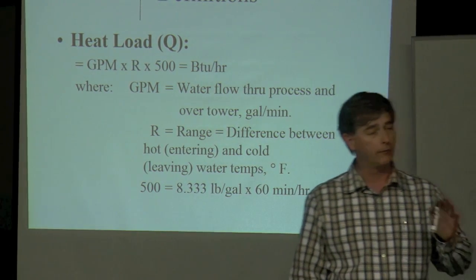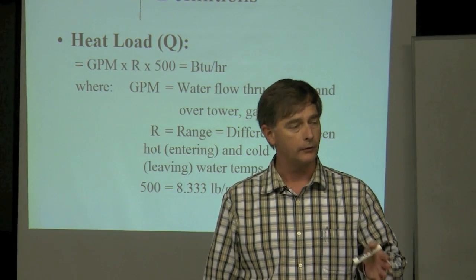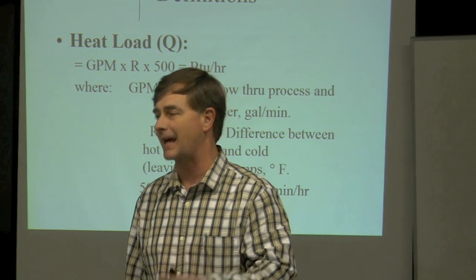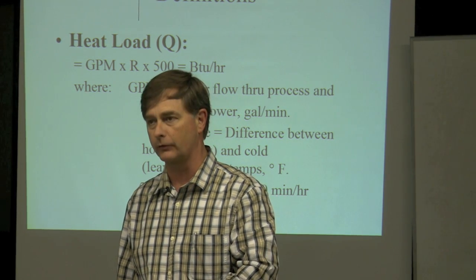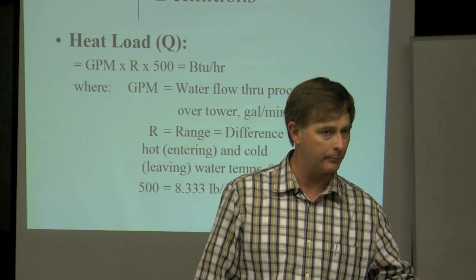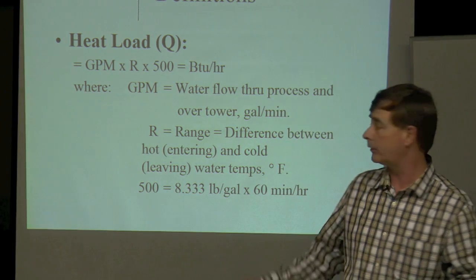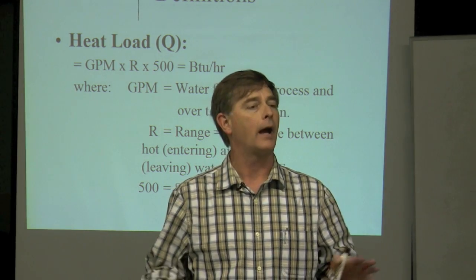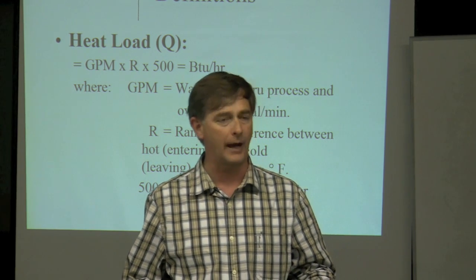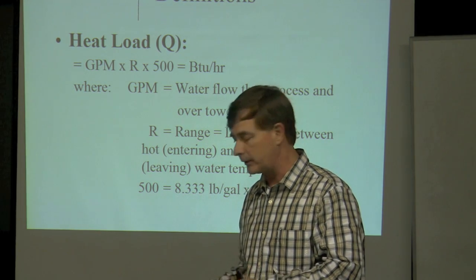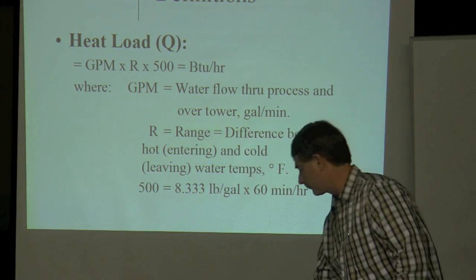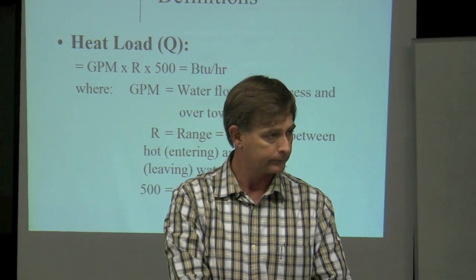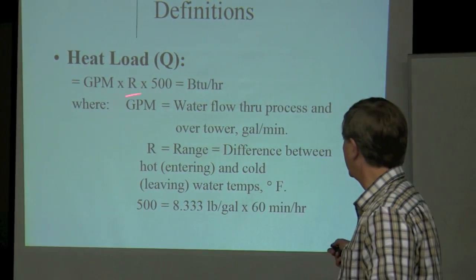On your formula sheet, I've given you some heat load formulas. You can take a look on the cooling tower side. Understand that when we're looking at the size of a chiller, we're looking at it on the evaporator side, because that's what we're most interested in. If you want to apply that same formula to this side of the system, you can tell the performance of your tower. It's basically the same if you look at the BTU formula on your formula sheet — it matches that.